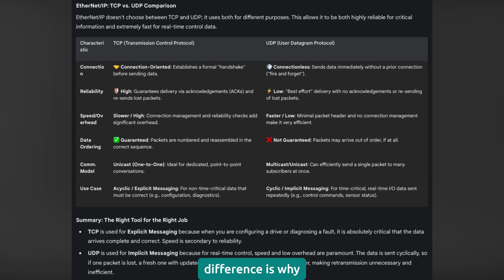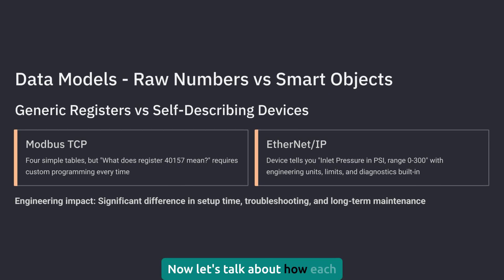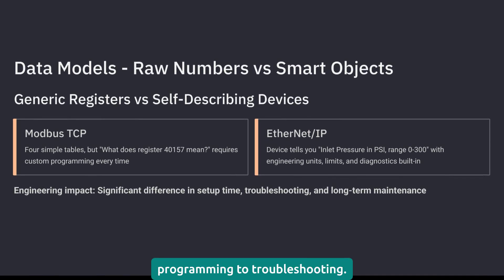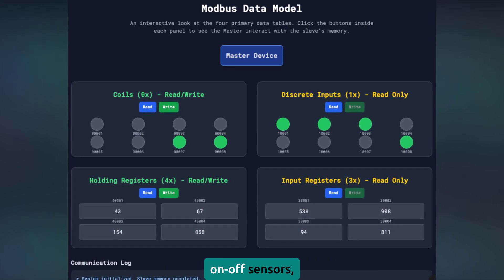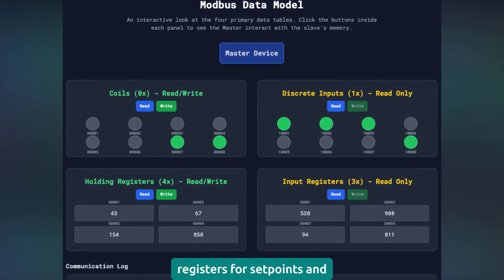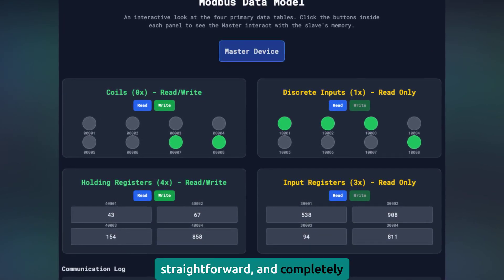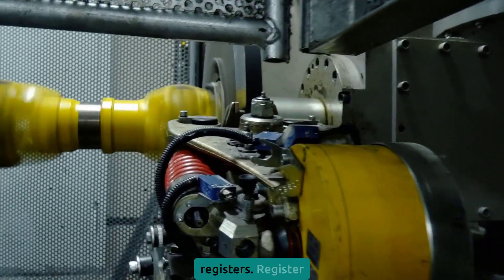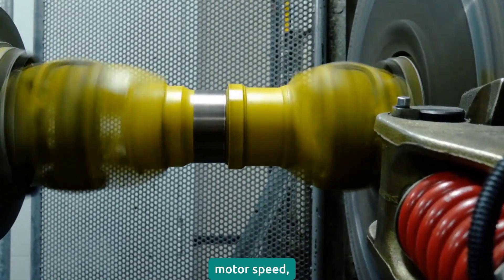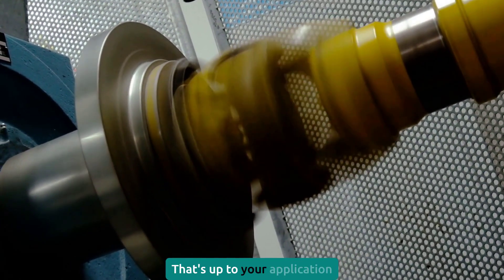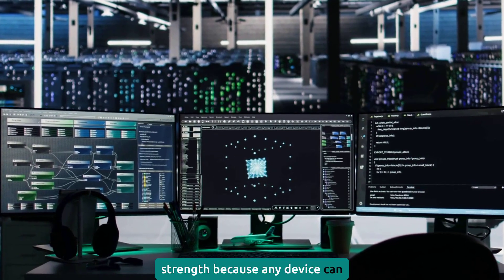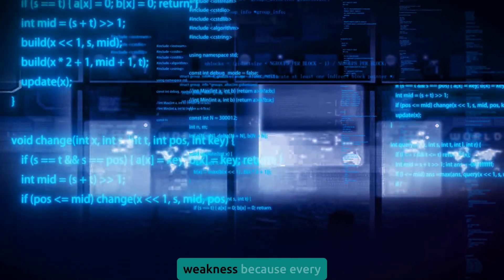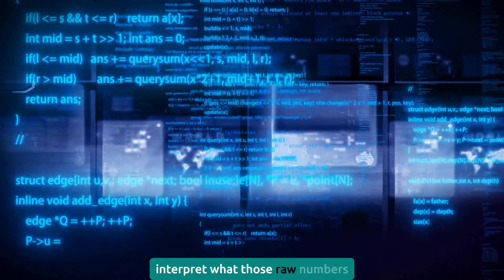This architectural difference is why EtherNet/IP can handle high-speed, synchronized control tasks that would bring Modbus TCP to its knees. Now let's talk about how each protocol thinks about data, because this affects everything from programming to troubleshooting. Modbus TCP sees the world as four big filing cabinets: coils for on/off outputs, discrete inputs for on/off sensors, input registers for measurement data, and holding registers for set points and configuration. The protocol has no idea what's actually in those registers — register 4001 could be motor speed, temperature, or pressure. This simplicity is both a strength and a weakness: any device can talk to any other device using the same basic commands, but every integration requires custom programming to interpret what those raw numbers actually mean.